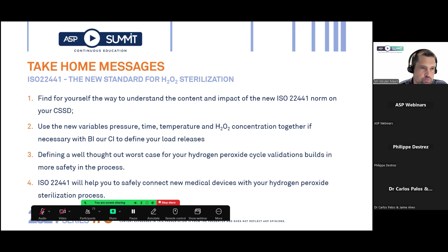So if we look at the take-home messages, first of all, find for yourself the way to understand the content and the impact of the norm. Take your time for it. Search for the people who can help you, manufacturers of sterilizers and your professional organizations, who will know how to reach. Use the new variables, pressure, time, temperature, and hydrogen peroxide concentration, together, if necessary, with BI and CI, to look at the load release and which way you can conduct it in your daily process. Define a well thought out worst case for your hydrogen peroxide cycle validation, and that's something you need to do to build in the most safety in your process.